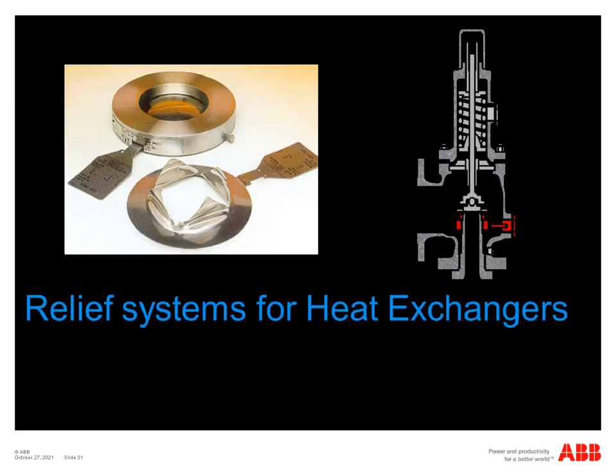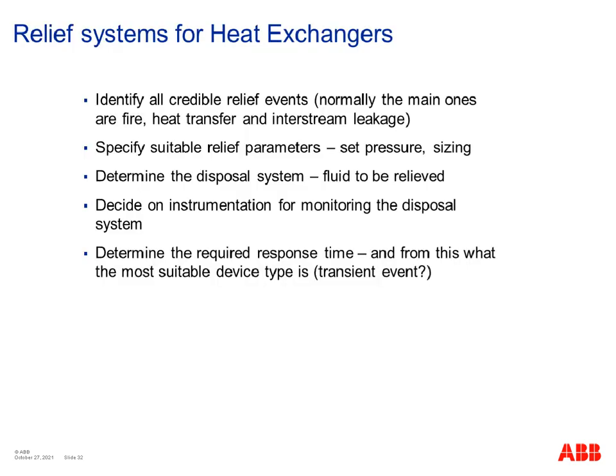So going into a summary for the relief systems for heat exchangers. What you would want to do is identify all your credible relief events. And as we discussed, I think more than once, the main ones are normally fire, heat transfer, and interstream leakage, although there may be others. You would specify suitable relief parameters. So you've got the set pressure of your relief device, and you think about the sizing of your relief device.